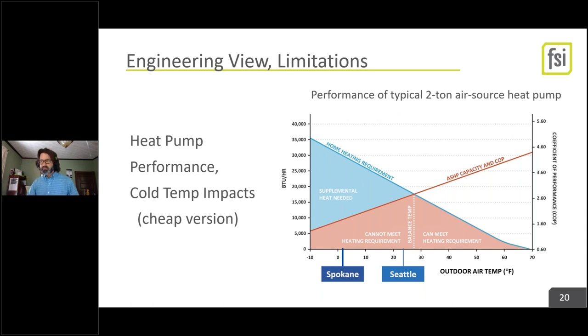So here's that graph. You hit 20, 25, and there's a Seattle design temp. You're living right there. Your air source heat pump capacity dropped a little. You're probably getting into backup heat. If you're in Spokane, if you're on the east side of the state, you're definitely backup electric heating. And the energy code covers that, allows it and has some limitations on it. Go for the next slide.